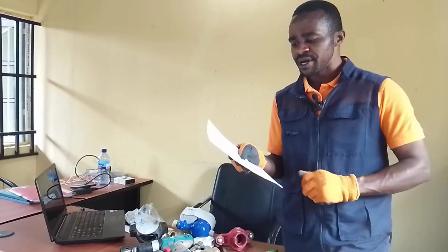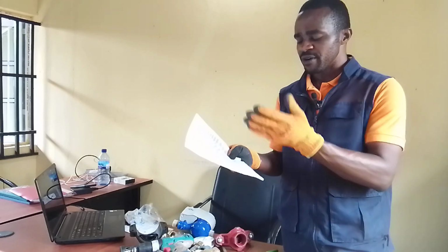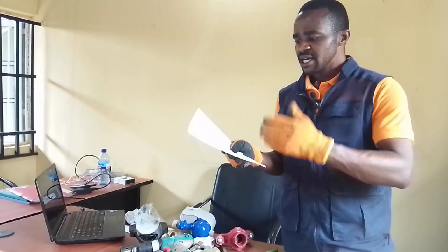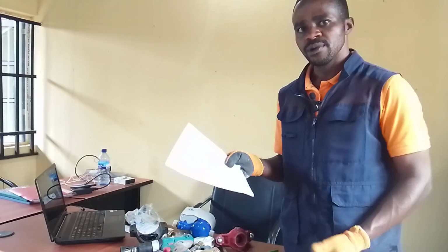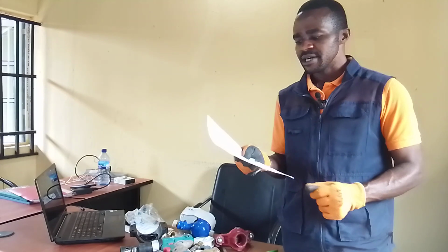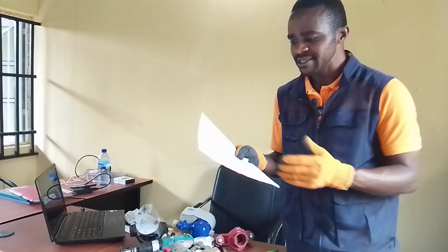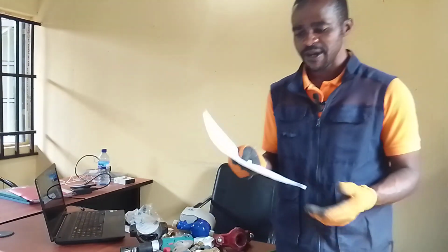So basically, in summary, if the pump is 1.5 horsepower, for instance, and the length is between 0 to 15 meters, you use a cable cross-sectional area of 1.0 millimeter square. From 16 meters to 30 meters, 1.25 millimeter square. From 31 meters to 60 meters, you use 1.5 millimeter square. And from 61 meters to 90 meters, you use 2 millimeter square.